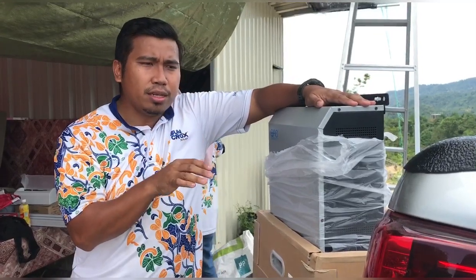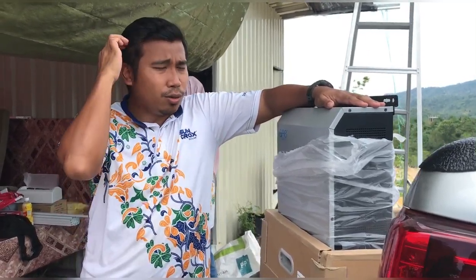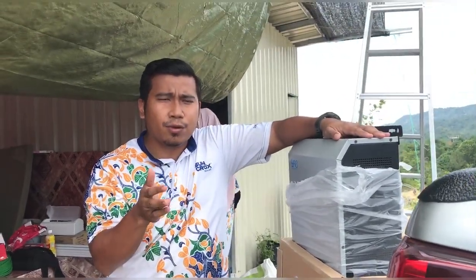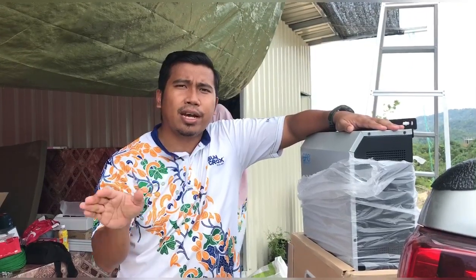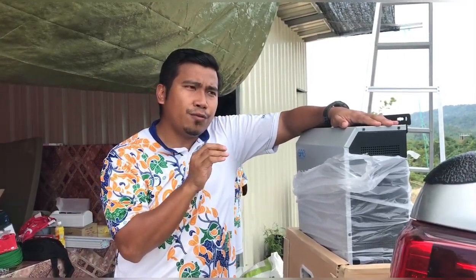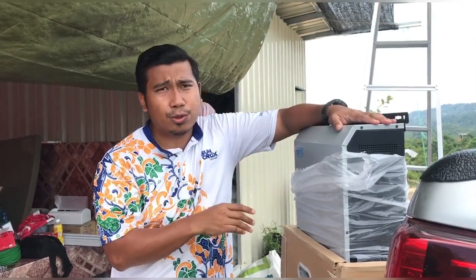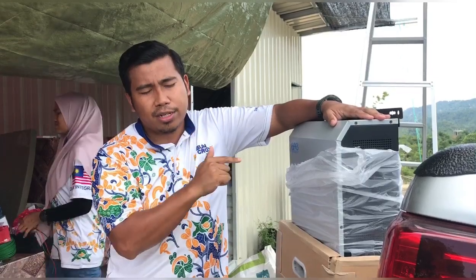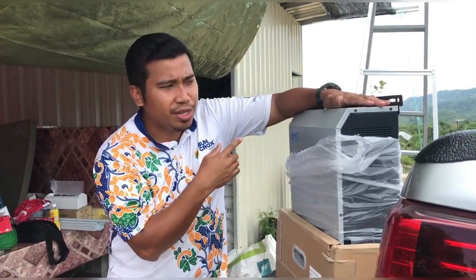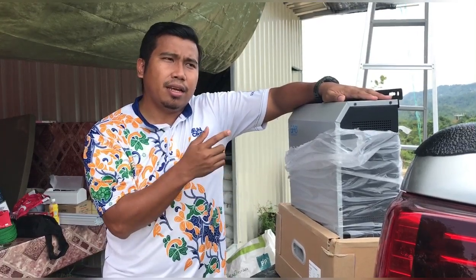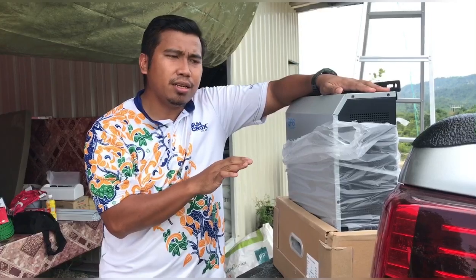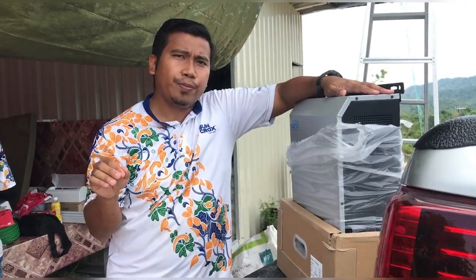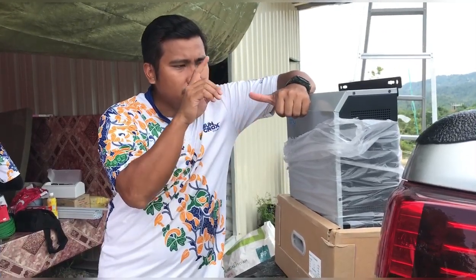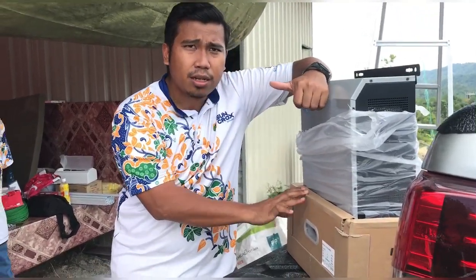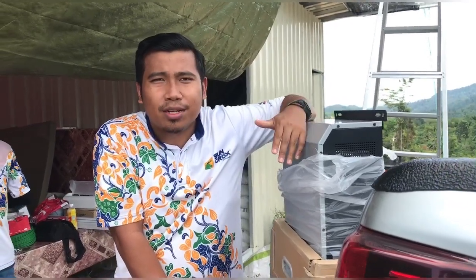But if you're using just for basic lighting, fans, for home appliances without any motor, you can use heating appliances like electric kettle, rice cooker and whatnot. You can use high frequency. But typically for anything with induction motor like water pump, you must use low frequency because low frequency has toroidal transformer inside. That's why it's very big, bulky and heavy. And the setback of using low frequency is actually the standby power is more than high frequency. Okay, so the disadvantage is high standby power consumption, but the advantage, you can use motorized equipment lah, water pump and whatnot.